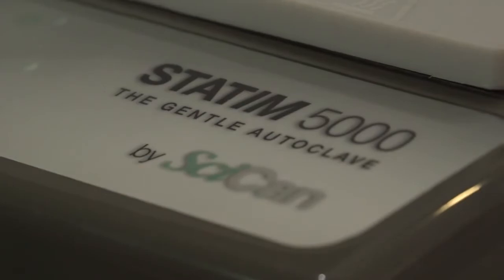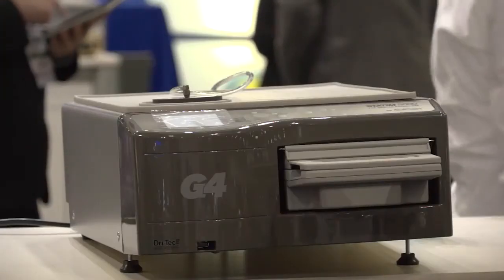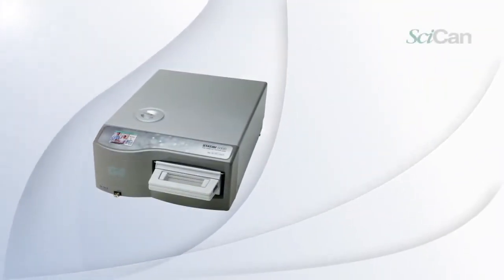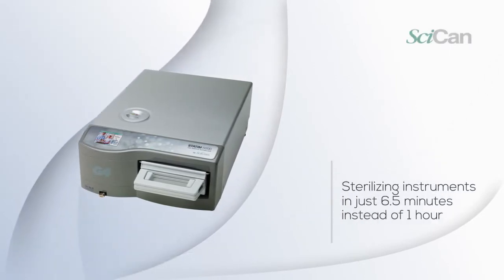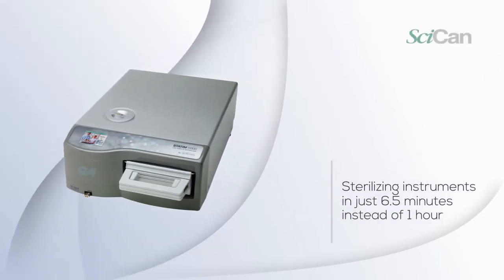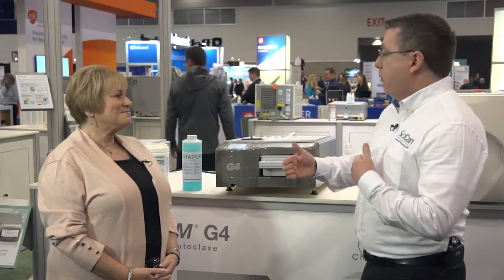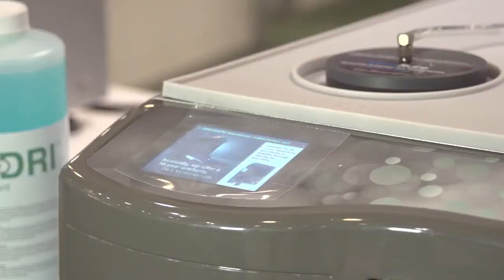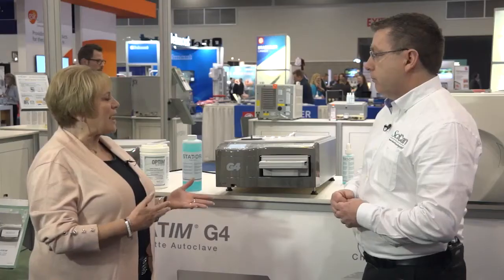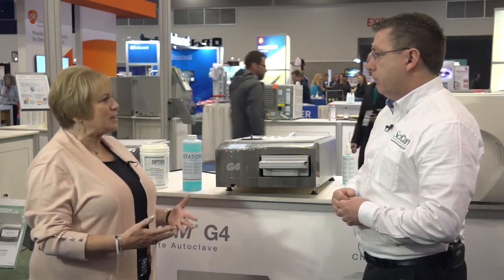Back in the early 90s, there became a need to sterilize instruments more repeatedly and more quickly. So things like handpieces up until the early 90s weren't actually sterilized. So the STATIM was designed as a handpiece sterilizer and to turn things over very quickly. From the time that you hit the start button to the time you could get the instruments back sterile was about 6.5 minutes, compared to a conventional sterilizer at the time, which could be almost an hour. Now that is a huge difference. It was, and it meant that the dental office could get by with fewer instruments because they could turn them over much more quickly. So how does an office benefit from having a STATIM if they also have a chamber autoclave?